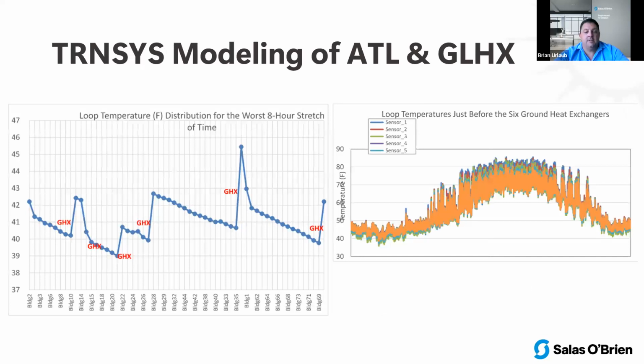We went through all the TRNSYS modeling again, showing the profile of the temperature loop and exactly what happens each time we inject energy, then how it drops back down as we hit all the buildings. This is a heating-dominant profile, somewhat balanced, but because of ground temperature we're still kind of heating dominant. We ran this in the middle of winter and our lowest point got down to about 39 degrees, then climbed back out and came back down. We could technically remove a few more bores from this field and let it drop a little further, but over the long term we have to ask what that sine wave looks like—does it build heat over time?